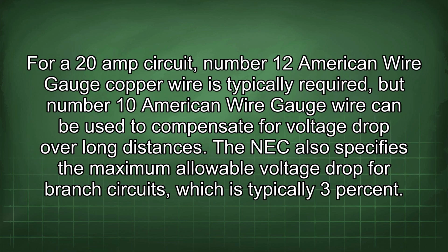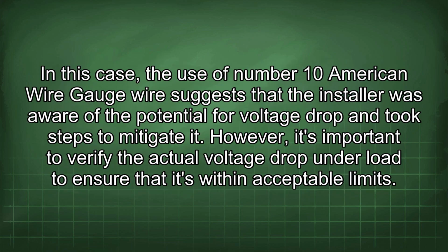For a 20-amp circuit, number 12 American wire gauge copper wire is typically required, but number 10 American wire gauge wire can be used to compensate for voltage drop over long distances. The NEC also specifies the maximum allowable voltage drop for branch circuits, which is typically 3%. In this case, the use of number 10 American wire gauge wire suggests that the installer was aware of the potential for voltage drop and took steps to mitigate it. However, it's important to verify the actual voltage drop under load to ensure that it's within acceptable limits.